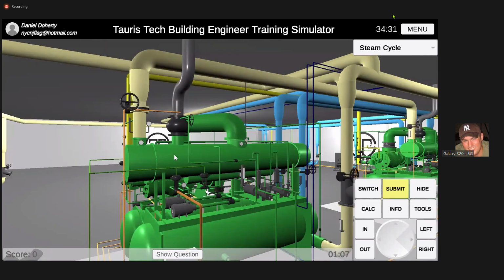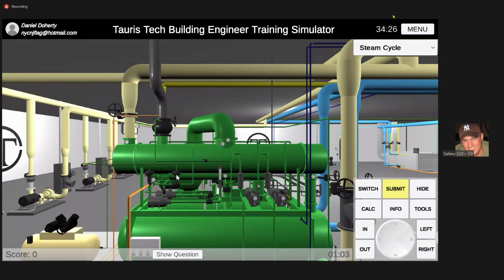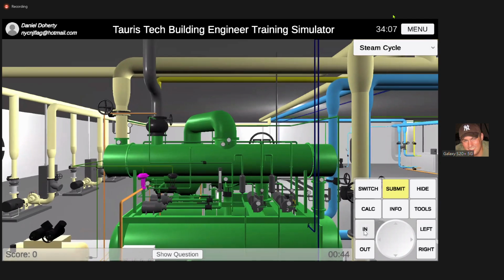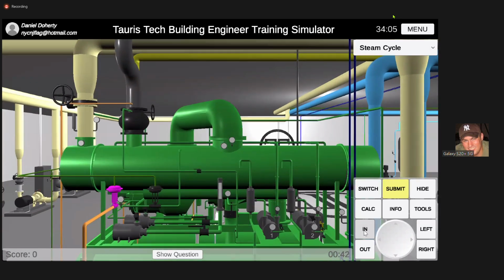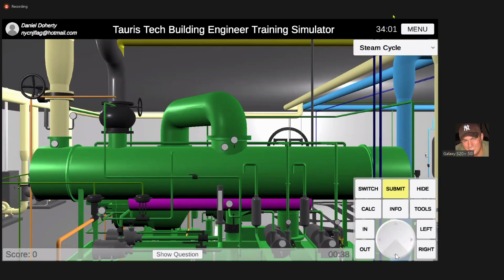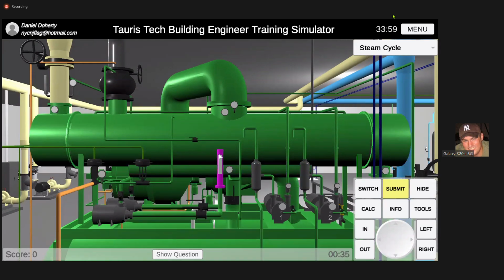It ends right here. And then these two valves right here determine what stays in the surface condenser and what stays in the hot well. This valve right here is your recirculation valve. And this is your overboard valve. On our simulator, they open and close based on this sight glass right here. Not the hot well, but that's that. Okay, this has a magnetic sensor in it. But on Metrotech, they don't use that. On Metrotech, there's a high float and a low float.